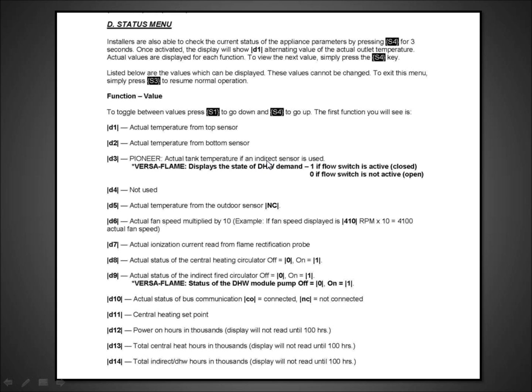When you go into a Versa Flame, the D3 now represents on the display 1 if the flow switch is active, which means it's closed and the pump is running, and 0 if the flow switch is not active and open. D9 tells you that on a Versa Flame, the DHW pump module is 0 equals off and 1 equals on. So I just wanted to point some of those facts out.